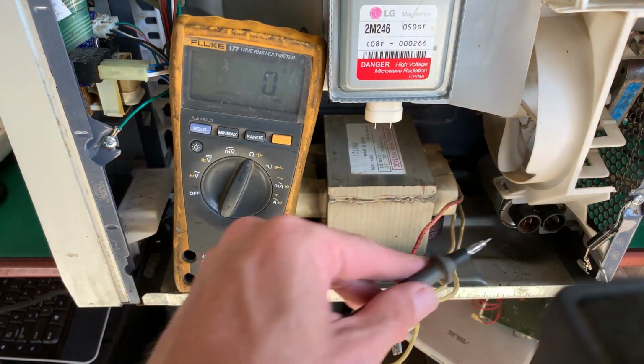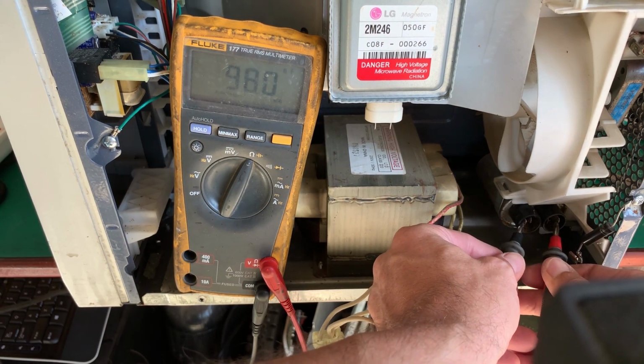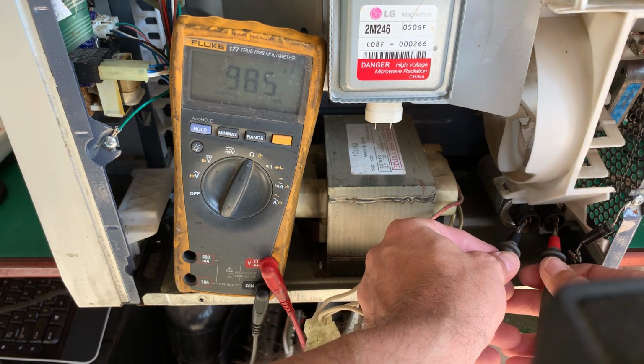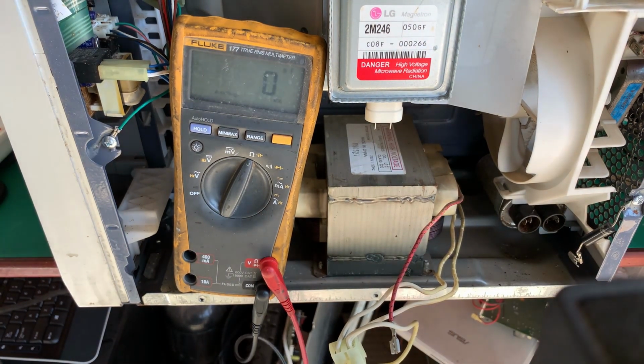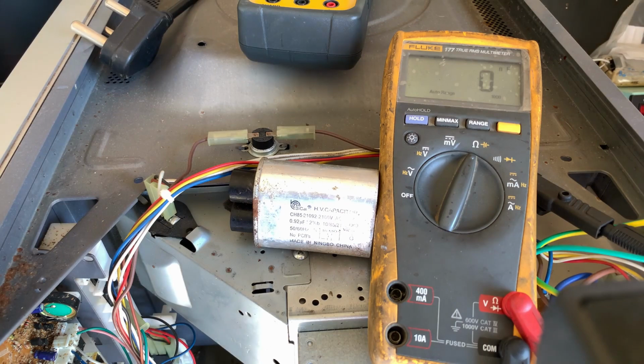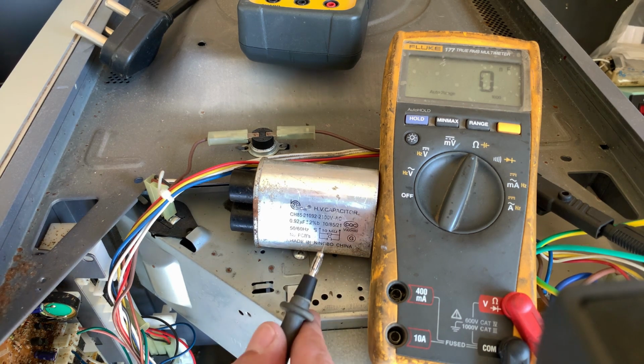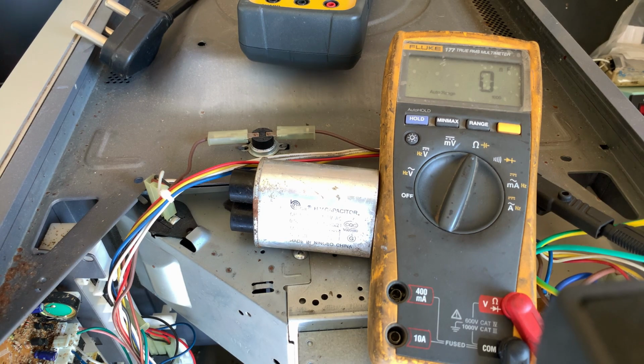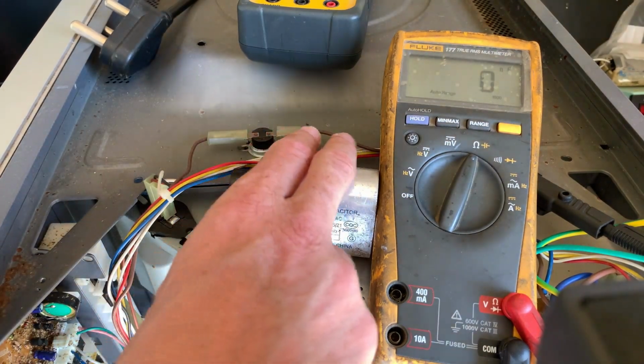Out of curiosity, I'm going to switch it to capacitance. And we're reading 980 nano. I'm not sure what the capacitance rating is of that capacitor, but what we'll do is we'll take it out and we'll have a look and we'll test it with our LCR meter, and we'll get a good idea from there what is going on. So let me take it out and we'll come back to that. Alright, so we've taken the capacitor out. As we can see, it's a 0.92 microfarad 2100 volt rated capacitor, and we can see in the little circuit down here it shows us it's got a 10 mega ohm resistor in parallel with the capacitor. That's our discharge resistor. Again, like I say, the multimeter is not the right way to do this. We'll use the LCR meter in a bit.